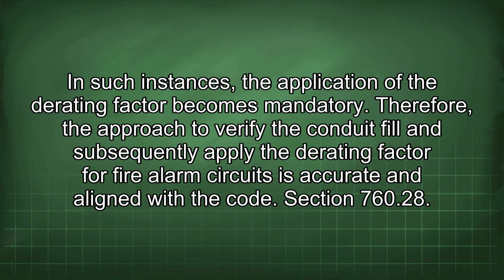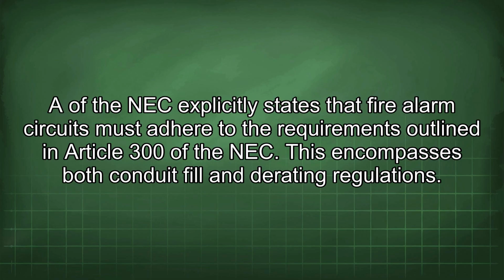Section 760.28 of the NEC explicitly states that fire alarm circuits must adhere to the requirements outlined in Article 300 of the NEC. This encompasses both conduit fill and derating regulations.